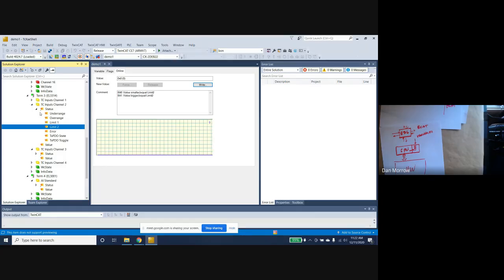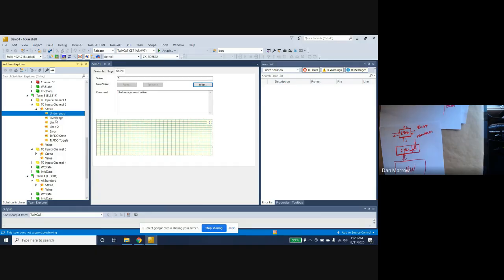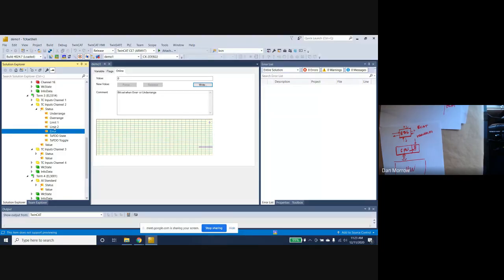So almost every slice is different in that respect, in terms of what it will tell you and what it won't. But even if something is simple - say, I just want to measure temperature - under range, over range, limits, errors - you go up to the Infosys system of Beckhoff, pull down the documentation on the slice, and you'll get 40, 50 pages on what's on the slice, what's in the slice, what do these bits all mean, what do you do with them.